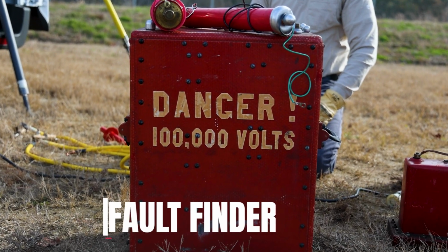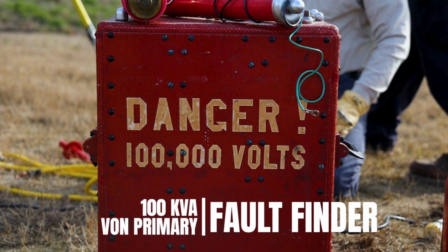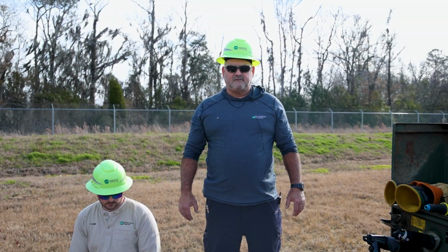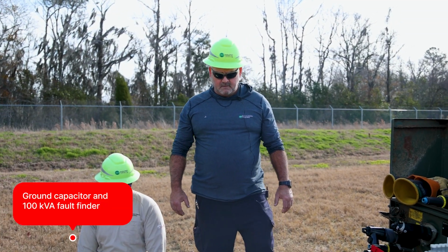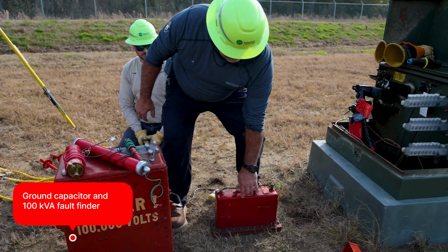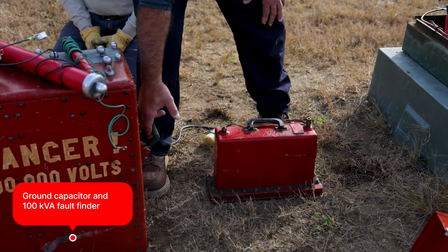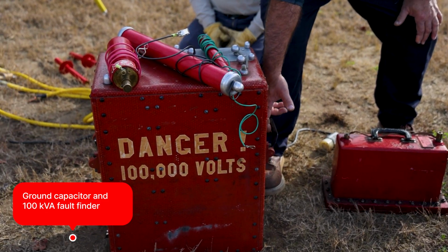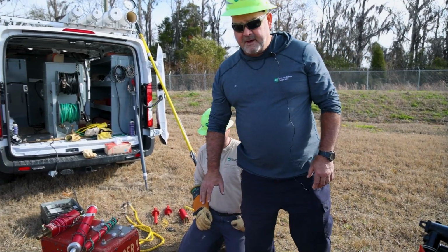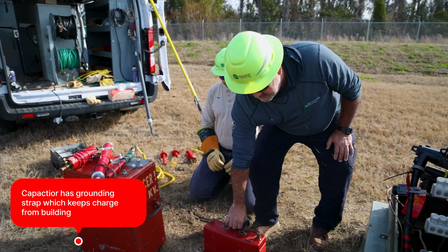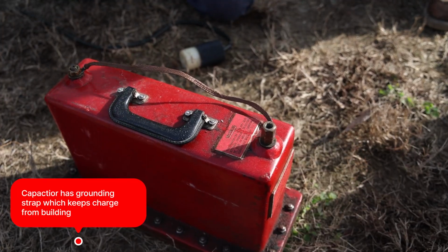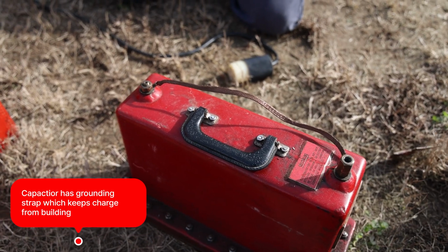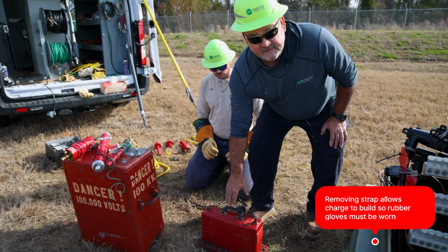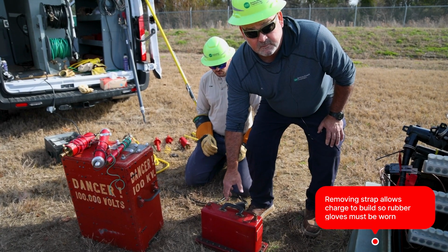This is a training video for the 100 kVA Vaughan primary fault finder. Step one, you need to ground the capacitor, which is this right here, and the 100 kVA fault finder. Right now it has a grounding strap, which is keeping any charge from building up. As soon as you disconnect this grounding strap, the capacitor can build a charge. So you need to wear your rubber gloves while handling the capacitor.